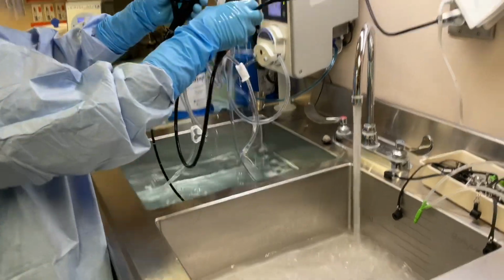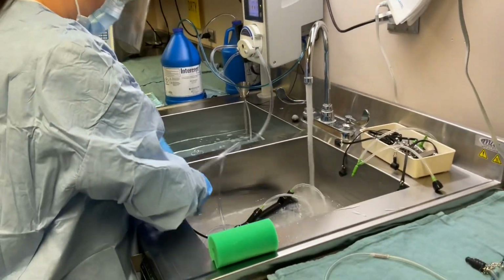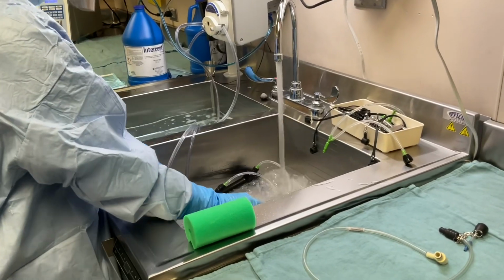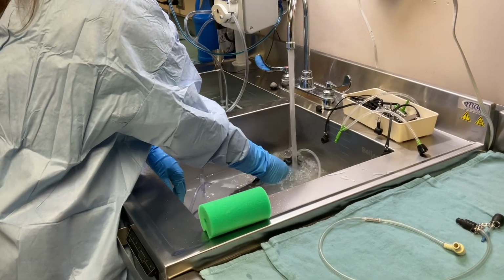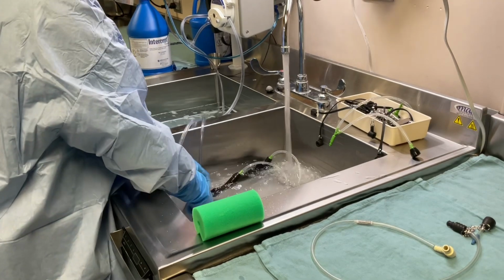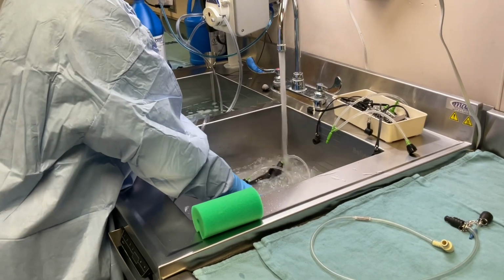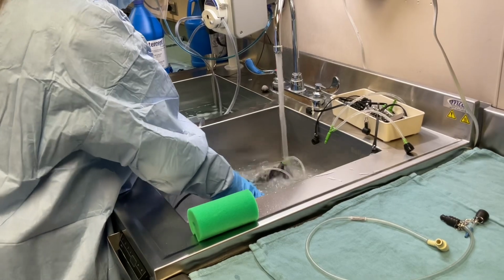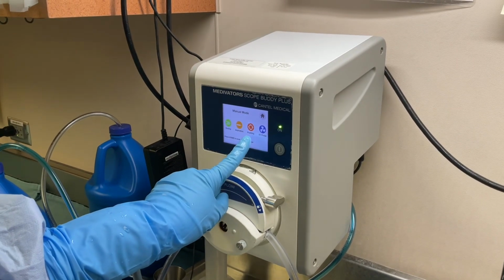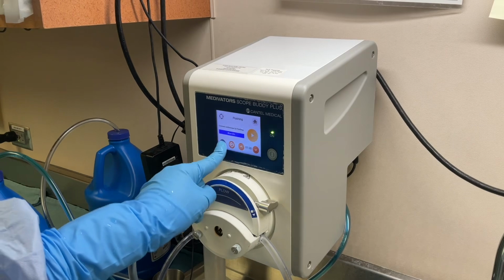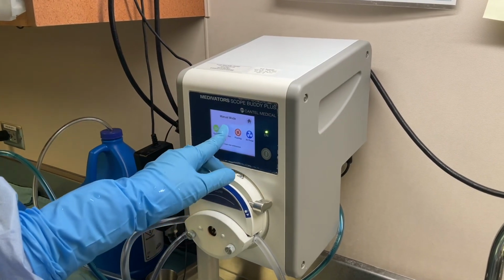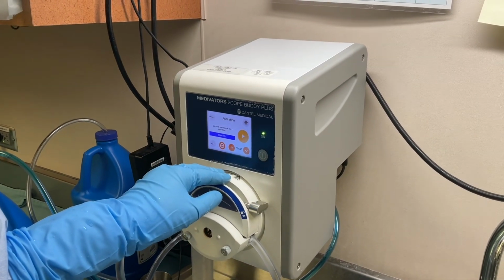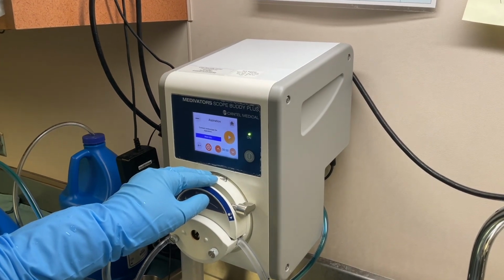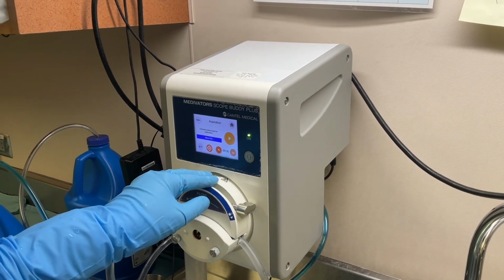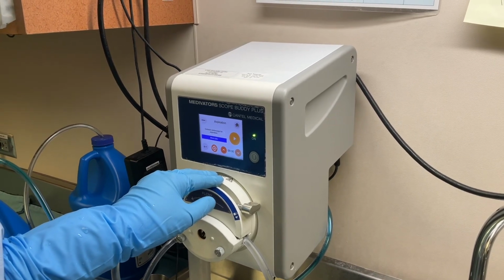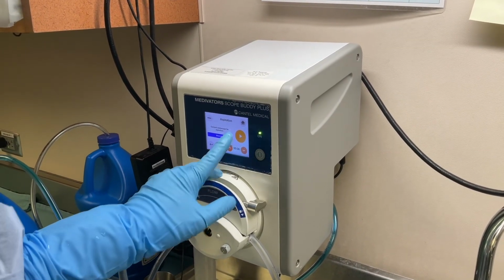Move the endoscope and all tubing to clean rinse water. Completely immerse and gently agitate the endoscope and tubing to thoroughly rinse. On the Scope Buddy Plus flushing aid, press the back button to return to the aspiration phase. Position the end of the pump tube without the strainer over the sink. Press play to aspirate clean water through the instrument and suction channels for 30 seconds.